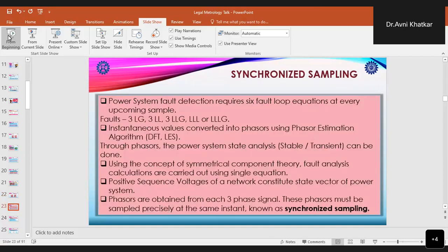So now when we talk about phasor measurement units, synchronized sampling comes into picture. And when we talk about synchronized sampling, we need to have all the samples of the grid. So for detecting faults, we require at least 6 fault loop equations for all the upcoming samples in the power system to see all the faults which are existing in the power system.